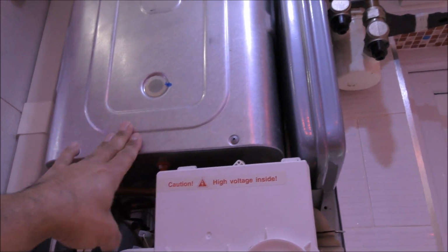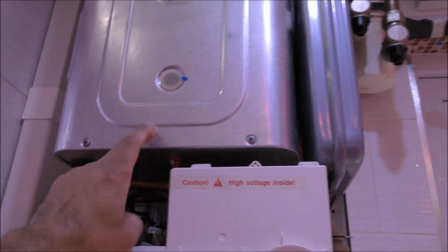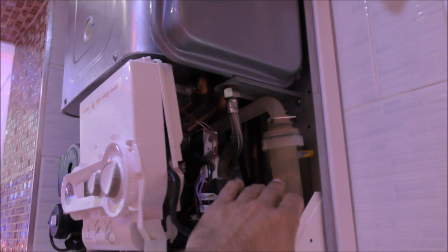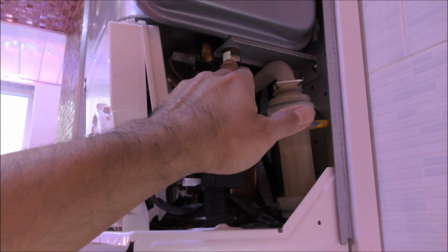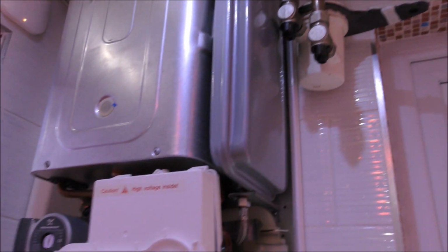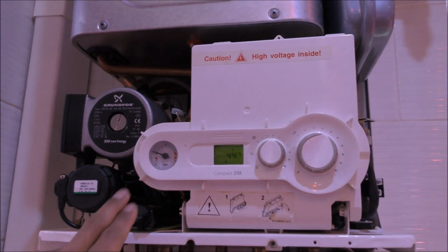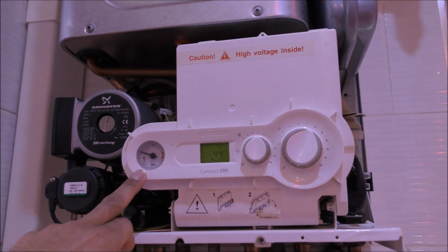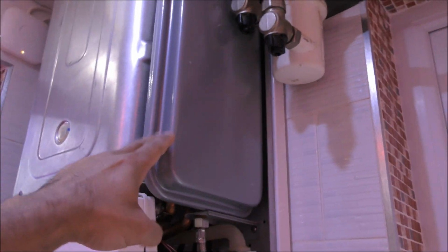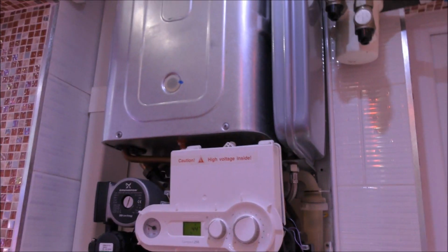As I said, repeating myself, if you hear any burbling or popping noise, you've got a blockage here somewhere, and this needs to be cleared. The other one needs to be cleared once a year too, that unit needs servicing as well. You've got to make sure this requires around about 1 bar of pressure, and 1 bar of pressure on the expansion vessel.